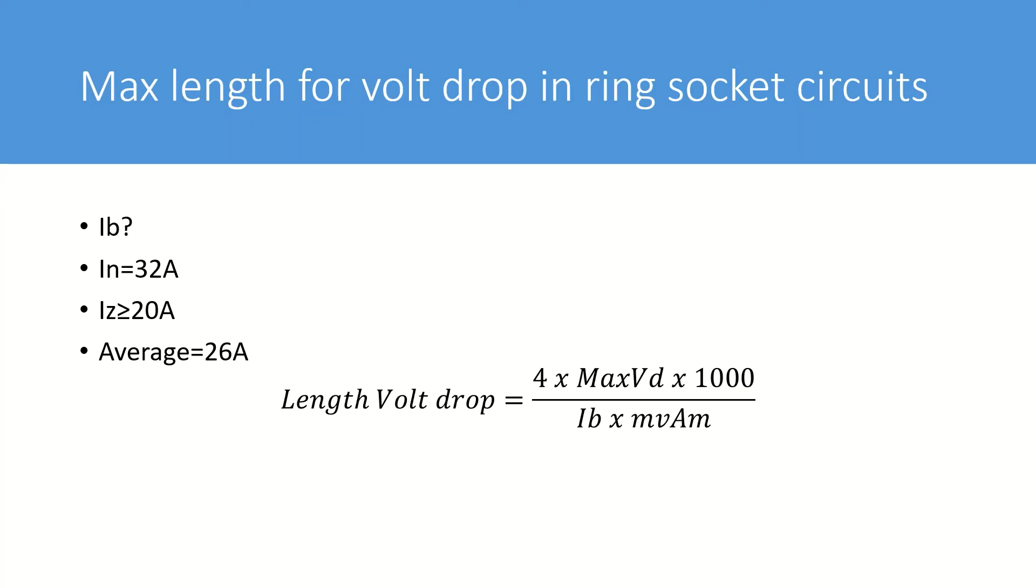The second difference is that because the circuit is wired in a ring when we are measuring to the farthest point of the circuit it's necessary to add a multiplier of four to the equation to allow for the loop of the circuit.